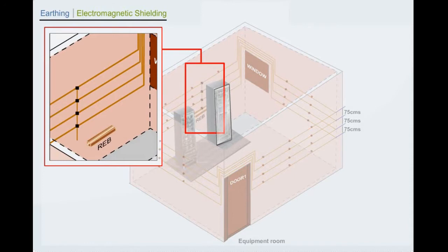Copper wires of each row are fully connected to REB of the Microlok 2 equipment room. By this, electromagnetic interference being induced in the room will be earthed. Thus, Microlok 2 equipment is protected.